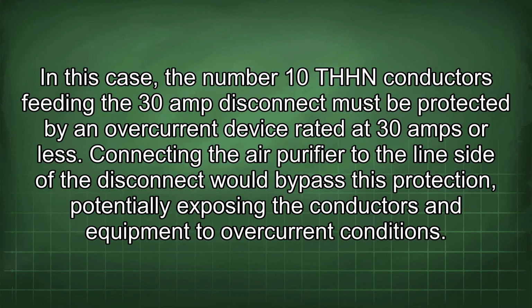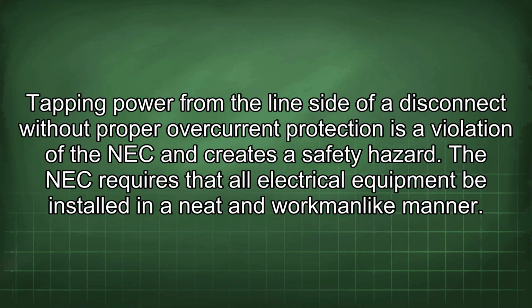In this case, the number 10 THHN conductors feeding the 30-amp disconnect must be protected by an overcurrent device rated at 30 amps or less. Connecting the air purifier to the line side of the disconnect would bypass this protection, potentially exposing the conductors and equipment to overcurrent conditions. Tapping power from the line side of a disconnect without proper overcurrent protection is a violation of the NEC and creates a safety hazard.